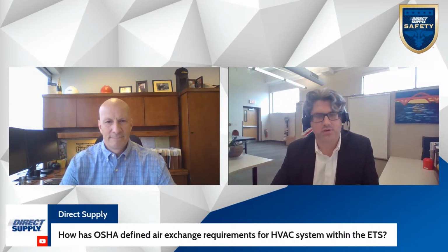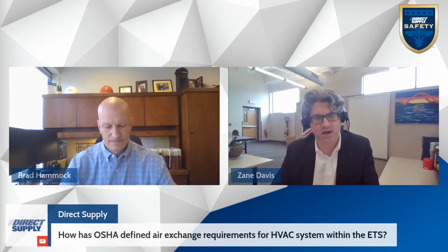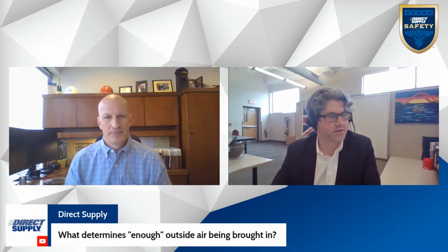Next question from the audience: how does OSHA define air exchange requirements for HVAC systems within the ETS? My understanding is that air exchange refers to air changes per hour, how much air you're moving through the space. They're not defining any specific requirement for any specific setting; they're saying you need to maximize the air changes per hour relative to how your system is designed. Is that the correct interpretation? Yeah, that's spot on. They're not saying you need 100 air exchanges or whatnot, they're saying maximize the air exchanges your system is designed to do.